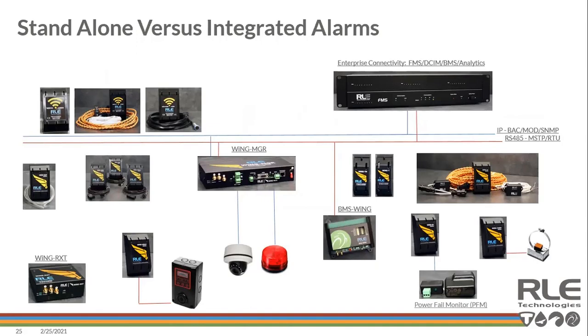But as we found in the other environment where the 10th floor penthouse was leaking, a little bit of thought and control logic was able to close a water valve and expedite fixing that massive problem for every floor below it. So this is more of a question - I don't expect everybody to answer this, but how are you alarming? What's your process when you do get an alarm? Are you dispatching service personnel, maybe another facility engineer, or calling a BAS group service team to come out?